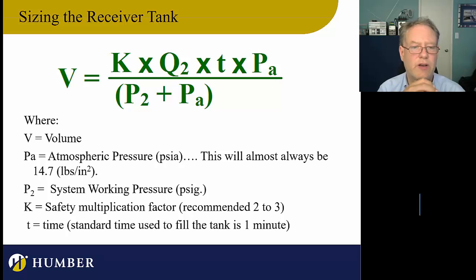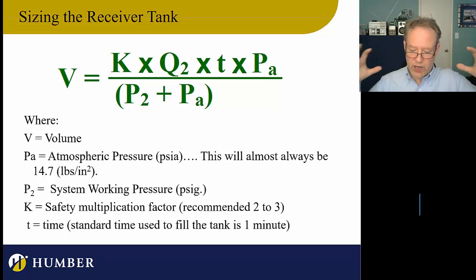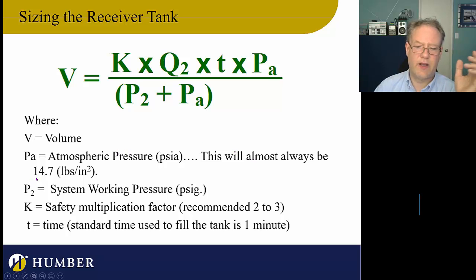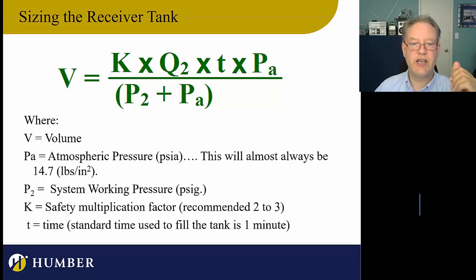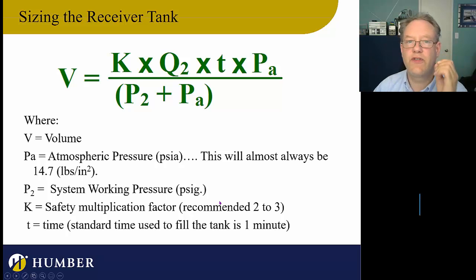V is the volume of the tank. PA is atmospheric pressure, and the system working pressure goes in as PSIG — the formula converts it to PSIA. The safety multiplication factor K is 2 or 3 — always at least double it. The standard time is about one minute: that's how long you want the compressor to run to fill the tank. The tank and compressor have to match — a tiny compressor with a huge tank won't fill it in time.